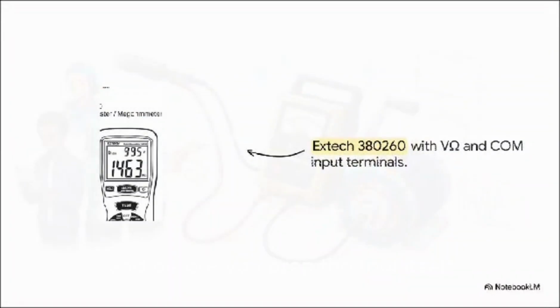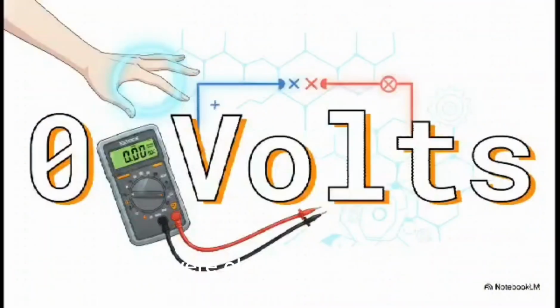And before you prep the tool itself, like if you're using an Extech 380260 or something similar, before you plug anything into those V, ohm, and COM input terminals, you have to inspect your actual gear. Your test leads and alligator clips have to be in absolutely perfect working order. They must be clean, and the insulation literally cannot be broken or cracked anywhere. Because if your leads are compromised, you're not just risking damaging the equipment, you are risking giving yourself a massive, severe electrical shock. So, before you move forward with any of your connections, this is your magic number: 0 volts. The circuit must read exactly 0 volts. It needs to be completely de-energized before you even think about touching it with your testing leads. If your meter detects AC voltage on the line, it's going to give you a constant warning beep. If you hear that beeping, you stop immediately.